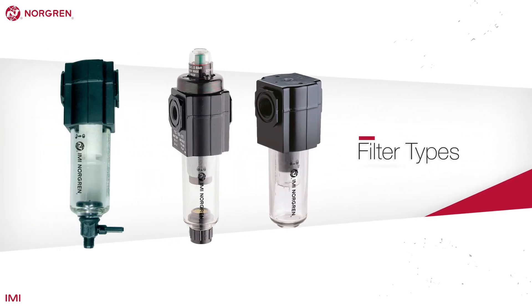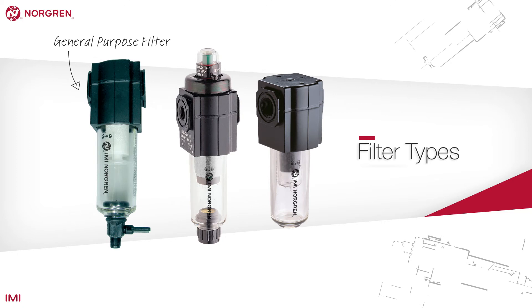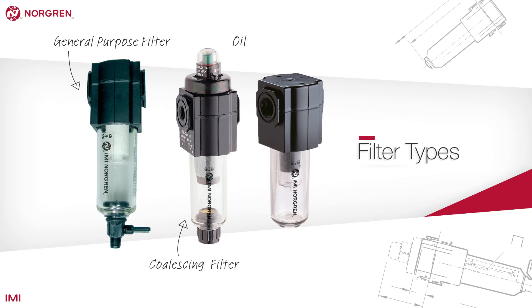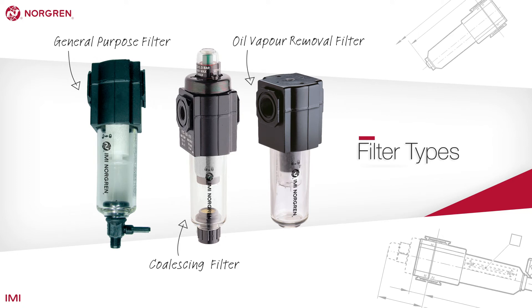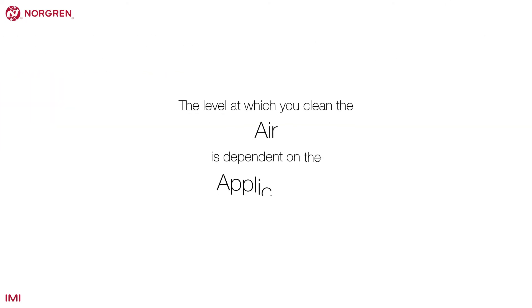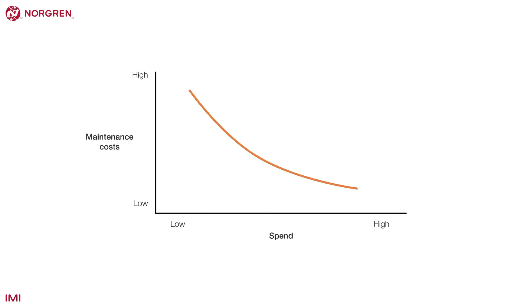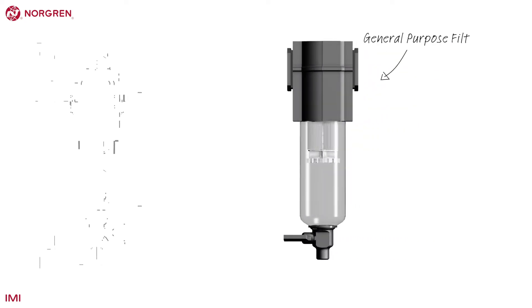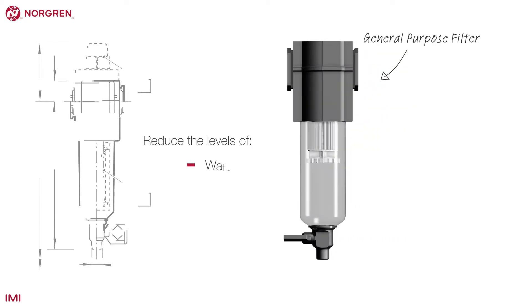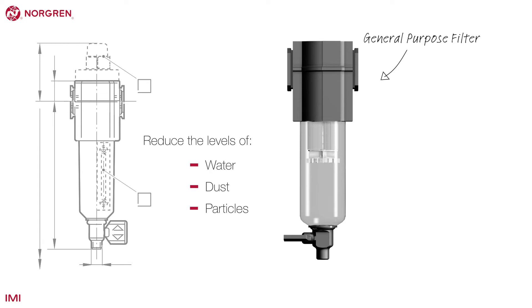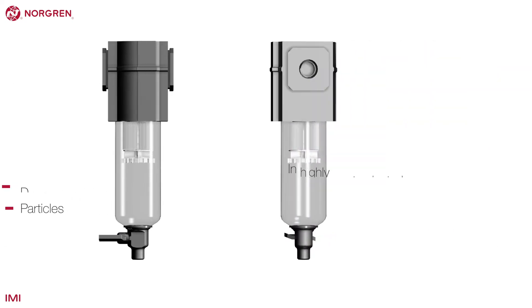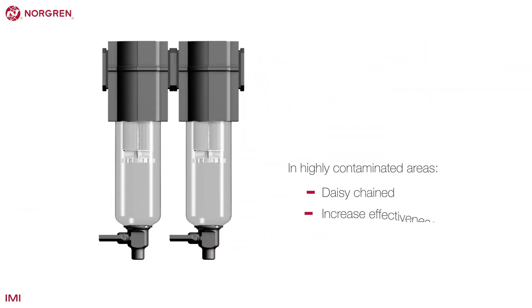Here are three filters: a general purpose filter, a coalescing filter and an oil vapor removal filter. The level at which you clean the air is dependent on the application, and the level of spend needs to be justified based on the reduced maintenance costs. A general purpose filter can be used to reduce the levels of water, dust and particles in compressed air. In particularly contaminated areas, they can be daisy chained to increase effectiveness.